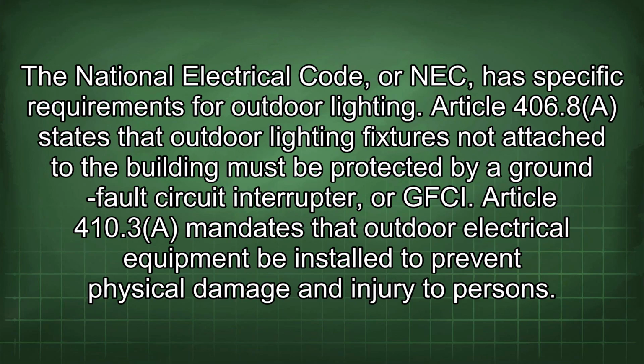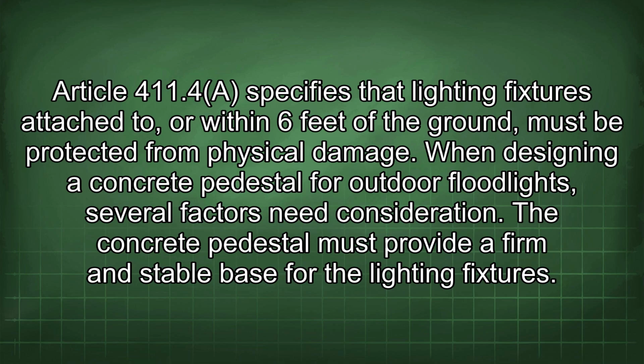The National Electrical Code, or NEC, has specific requirements for outdoor lighting. Article 406.8 states that outdoor lighting fixtures not attached to the building must be protected by a ground fault circuit interrupter, or GFCI. Article 410.3 mandates that outdoor electrical equipment be installed to prevent physical damage and injury to persons. Article 411.4 specifies that lighting fixtures attached to, or within 6 feet of the ground, must be protected from physical damage.